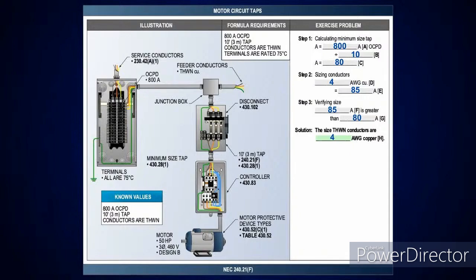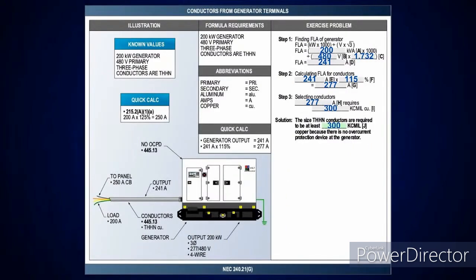Now, if I go over and I look at table 310.16, I come down and pick up my 75 degree C column. The next size above that's 85 amps, which is a number 4 conductor. So therefore, the size conductors are required to be a number 4 copper. But if you notice, did I change anything that I've said up to this point about doing a tap? No. Kept it all the same. Did not do one thing different.